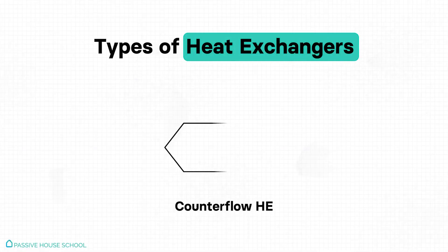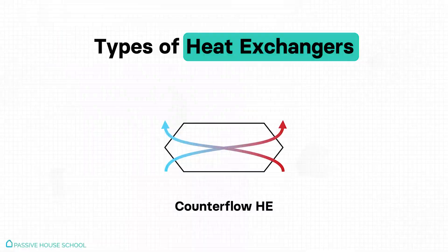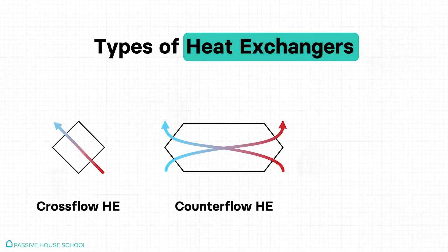Be careful with the unit you choose and what type of heat exchanger it has. Firstly, we have counter flow exchangers, where the two air streams flow in opposite directions, allowing for maximal heat exchange efficiency. These can reach heat recovery efficiencies of up to 93 percent.